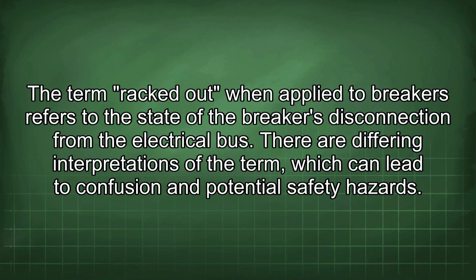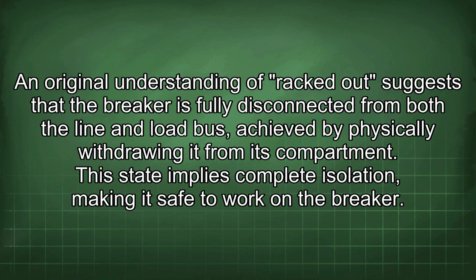The term racked out, when applied to breakers, refers to the state of the breaker's disconnection from the electrical bus. There are differing interpretations of the term, which can lead to confusion and potential safety hazards. An original understanding of racked out suggests that the breaker is fully disconnected from both the line and load bus, achieved by physically withdrawing it from its compartment. This state implies complete isolation, making it safe to work on the breaker.